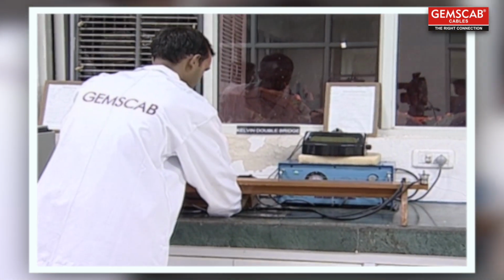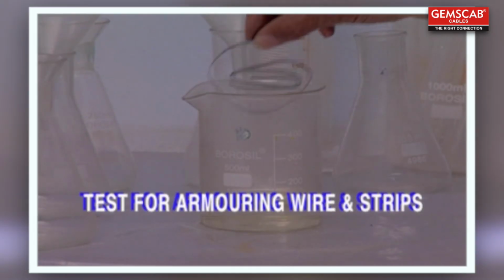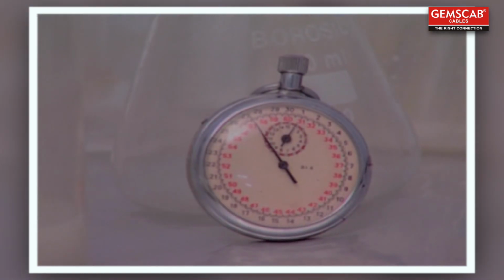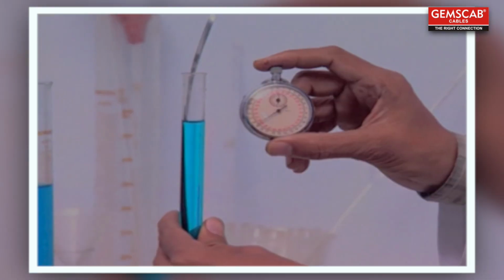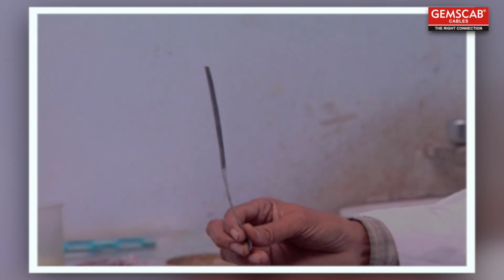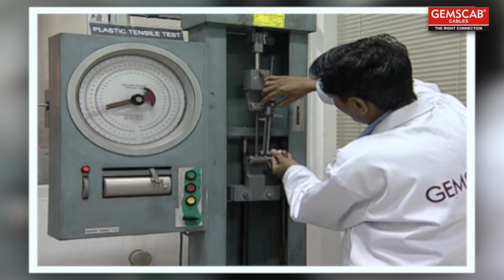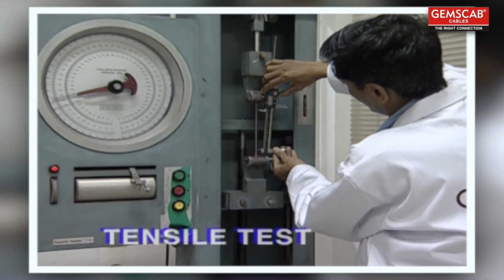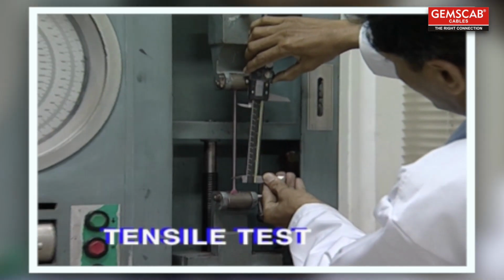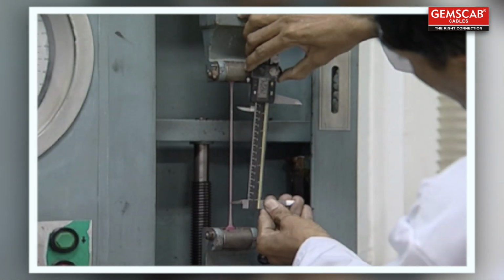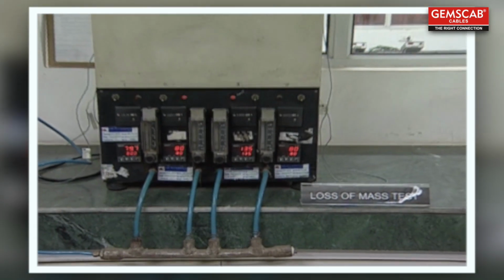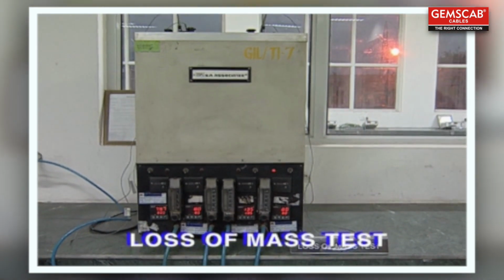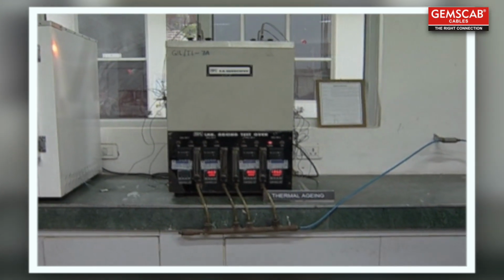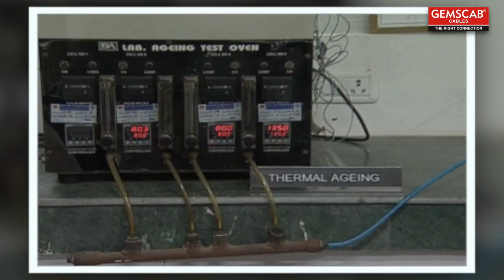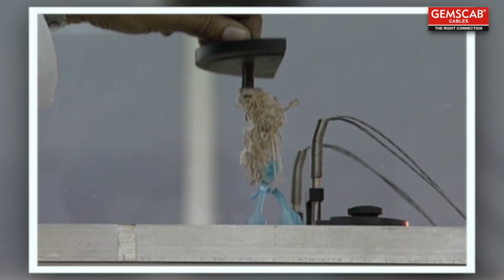Thereafter, the cables are tested to check resistance of the armor. Armoring wires and strips are tested for requisite mass of zinc coating on the steel. The armoring wires and strips are tested for uniformity of zinc coating. Physical tests are then carried out to ensure requisite tensile strength and elongation properties of the insulation sheath to withstand stresses and strains. This is followed by loss of mass test that confirms the lifespan of insulation and sheathing material by aging the conductors in an air oven.